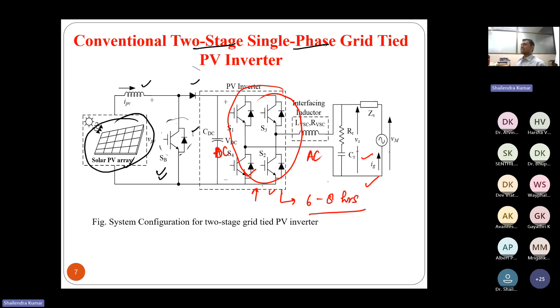Out of 24 hours, we are able to utilize only 6 to 8 hours, because we should get sufficient voltage here so that this inverter can generate sufficient voltage at the output of this unit. Otherwise, your grid will not be synchronized. So under low generation conditions, when the generation is very low in the morning, sometimes the inverter may not switch on. It will be tripping continuously.